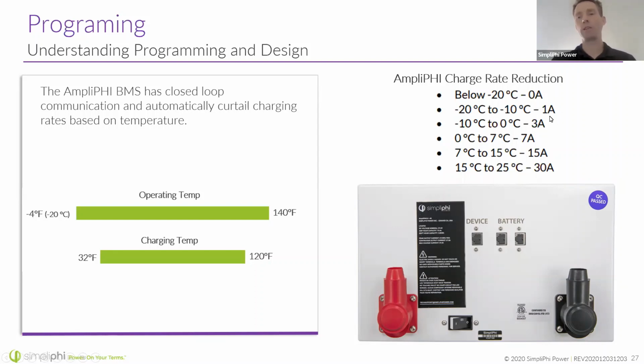That's only about 3% of the typical charging capacity of the battery, right? And -10 to 0 Celsius, we're about 10% of the charging rate. And so the SimpliPhi BMS unit controls the charging rate to make sure that the battery's state of health is maintained. And so even though we say that the charging temp is this, it's actually slightly elevated, so it's a slightly larger charging range. And then the discharge range is not as much affected by temperature, because then the lithium ions are going the other direction. So the operating temperature is what we really mean is the discharge, the time when the battery's providing power to the inverter and supplying loads.